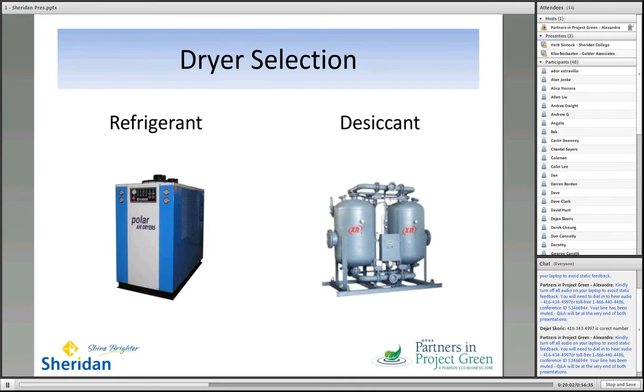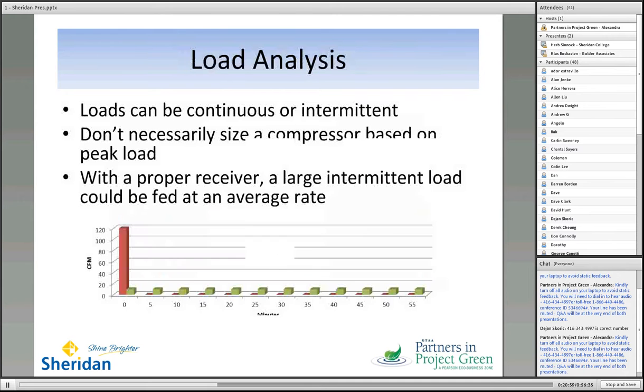But another consideration in this is picking the right dryer in the first place. A refrigerated dryer is going to get you a 35 to 39 degree Fahrenheit dew point. The idea of that is to avoid situations where water is condensing out of the air in your plant. A twin tower desiccant dryer, like you see on the right, is a minus 40 degree F dew point. And really it's about pharmaceutical grade stuff. It's about when you need very, very dry air for your process. Even things like painting could be handled with a refrigerated dryer, moisture and air-water separators, and good filters with fine particulate filtering to remove all that entrained moisture. You don't necessarily need a desiccant dryer to do it. The issue with the desiccant dryer is that you've got about a 15% energy penalty for using it.